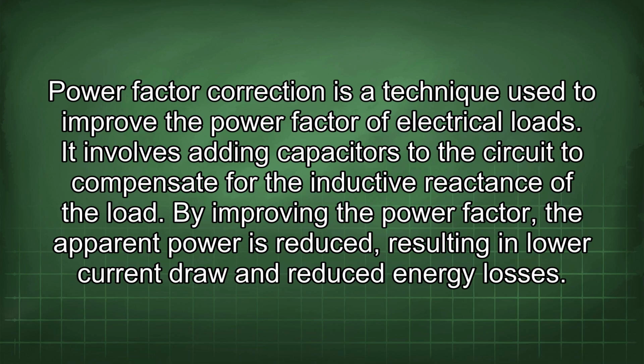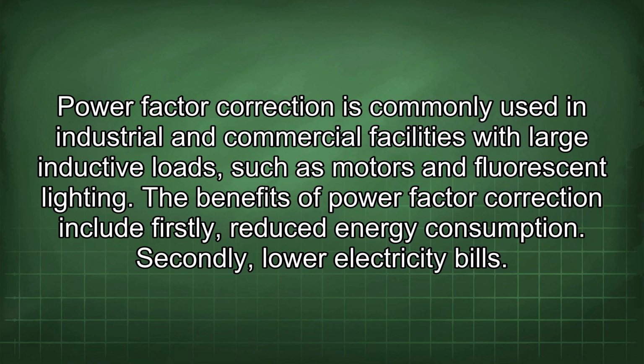Power factor correction is a technique used to improve the power factor of electrical loads. It involves adding capacitors to the circuit to compensate for the inductive reactance of the load. By improving the power factor, the apparent power is reduced, resulting in lower current draw and reduced energy losses. Power factor correction is commonly used in industrial and commercial facilities with large inductive loads, such as motors and fluorescent lighting.